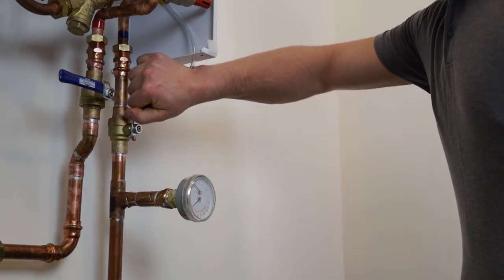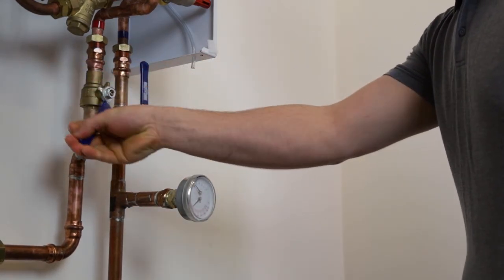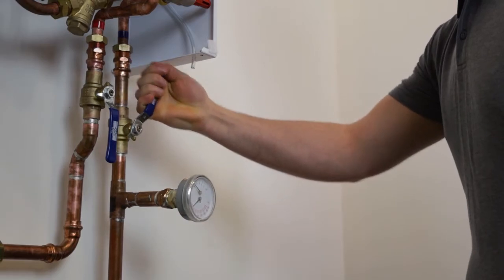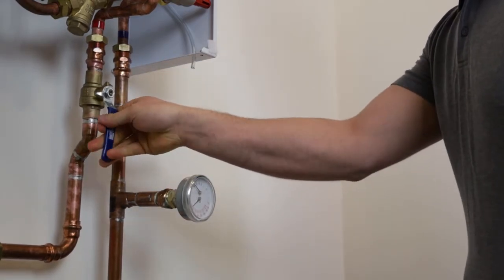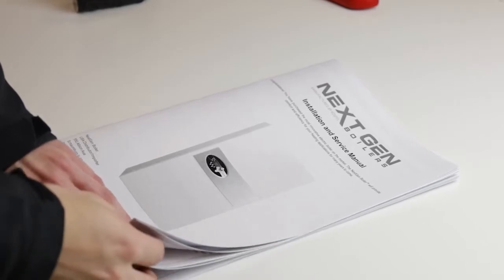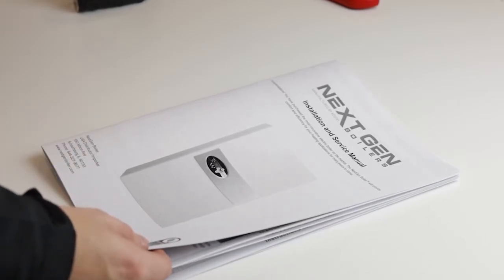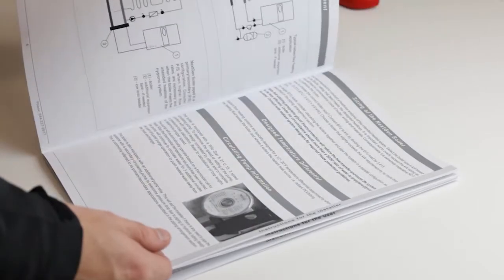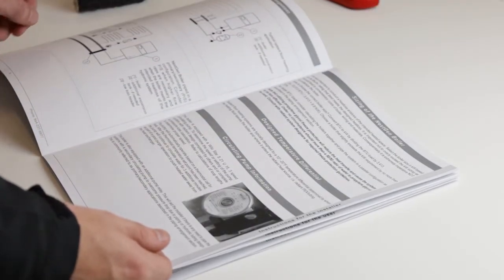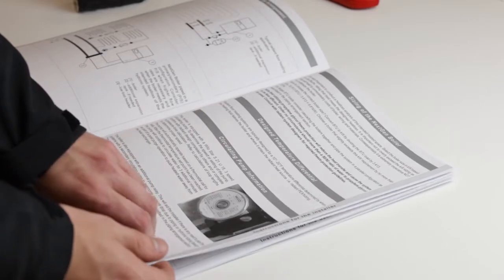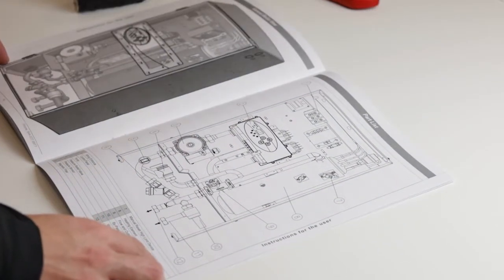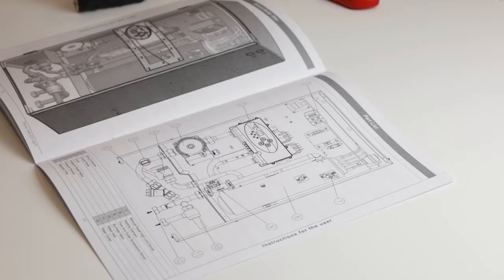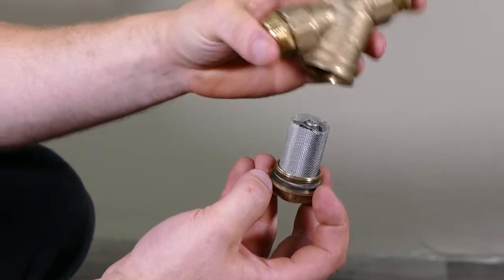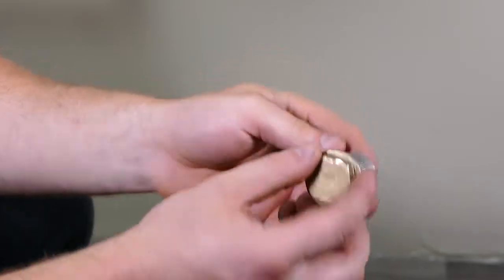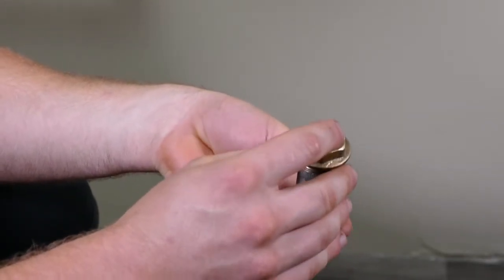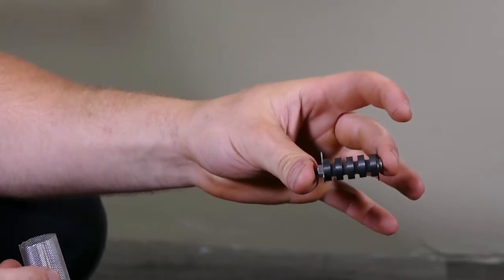When plumbing your water connections, we highly recommend installing flow and return valves. This will allow for easier access to the boiler if the need arises in the future. We always recommend to first power flush the boiler and the related hydronic components prior to final filling and pressurizing. Water quality is critical for a closed-loop hydronic system. You should aim for a pH level between 6 and 7 to extend the longevity of the boiler. After flushing the system, make sure to clean out the magnetic filter prior to the final filling.